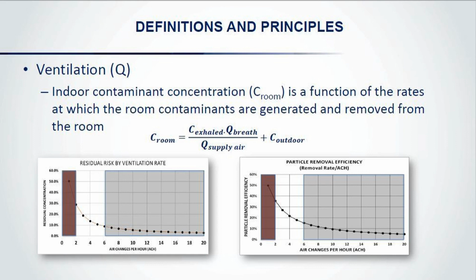Your indoor contaminant concentration is a function of the rates at which room contaminants are generated and removed from the room. What I'm trying to show you in those two graphs, which go right up to 20 air changes, is that there's always some residual risk, some residual contaminant level. No matter how much you ventilate, there's always some risk. Your risk never goes down to zero. Your rooms are never safe.